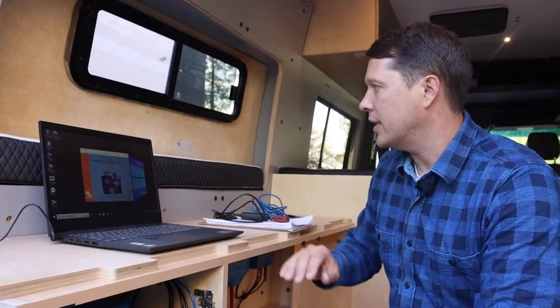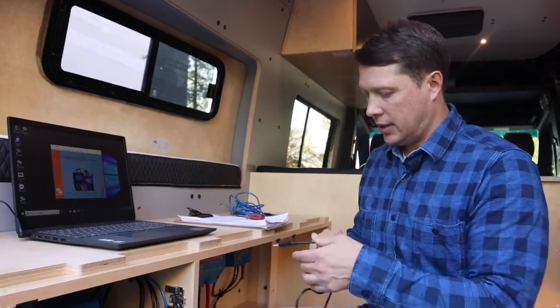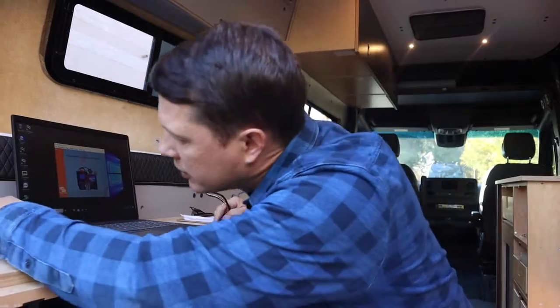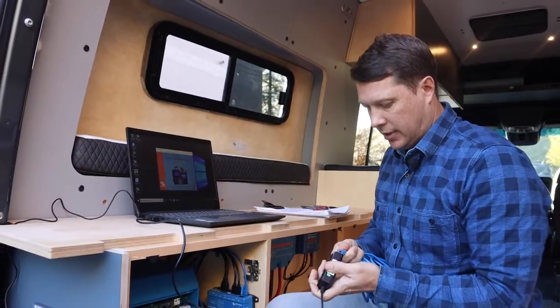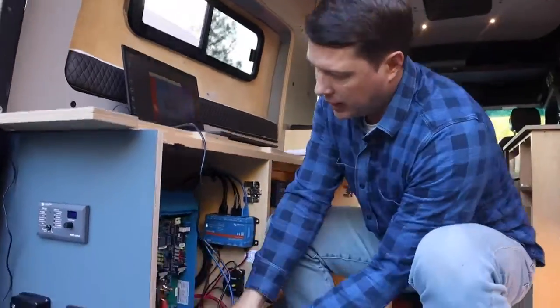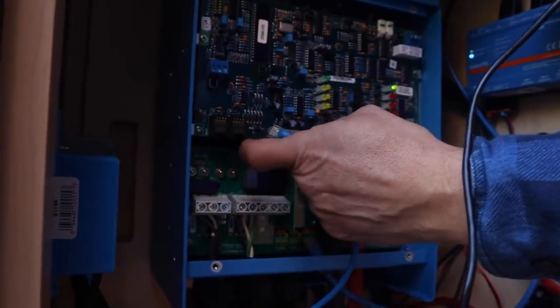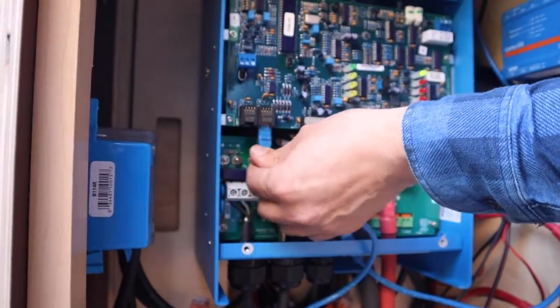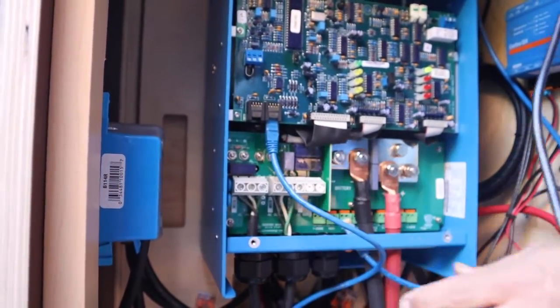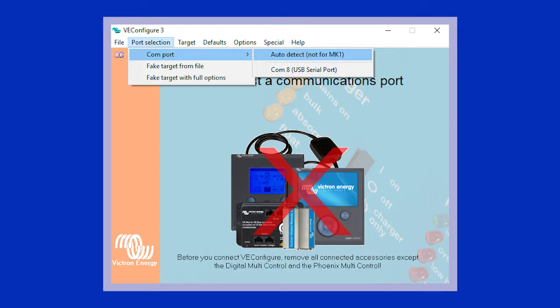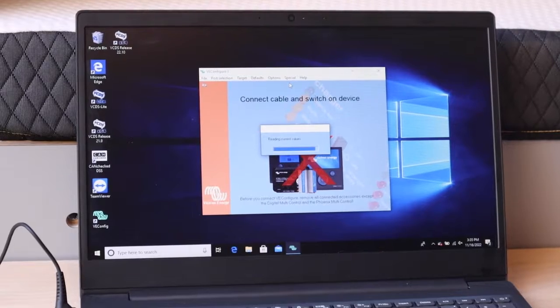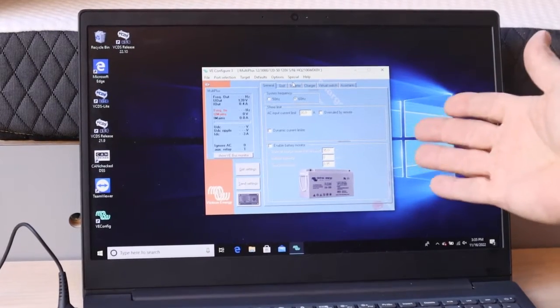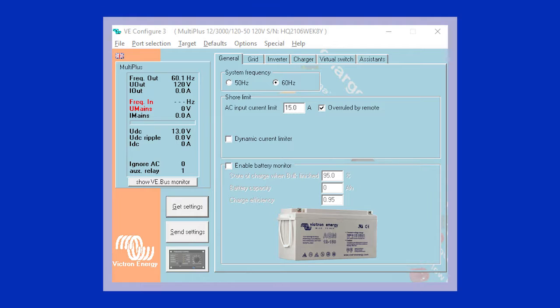So first step, it says, please select a communications port. So we're gonna take the unit, plug it into one of our USB outlets, and then we will plug the RJ45 into this. And then the unit here has 2 different ports where you can put in the RJ45 cables, and both of them are the same. They do the same thing, so don't worry about which one it is. Plug that in. We're gonna go to port selection up here in the top menu, select COM port, and then auto detect. And right now it seems to have found the unit, so it's going through and taking all of the current readings, and there we have it. So once you get to this screen, you know that you're going to have connected to the unit.